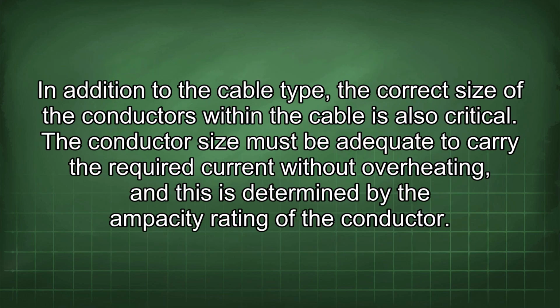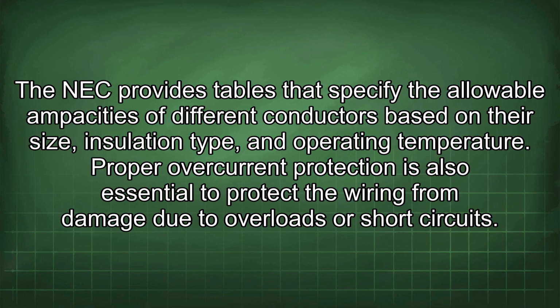In addition to the cable type, the correct size of the conductors within the cable is also critical. The conductor size must be adequate to carry the required current without overheating, and this is determined by the ampacity rating of the conductor. The NEC provides tables that specify the allowable ampacities of different conductors based on their size, insulation type, and operating temperature.